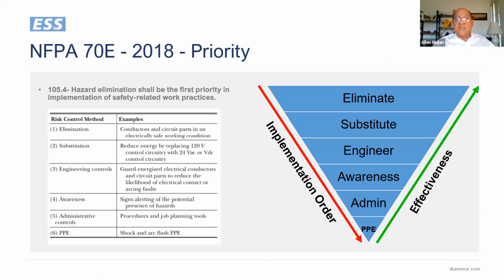The 2018, which is the latest version, has identified the priorities. This is new in 2018. It says use the hierarchy of control: elimination, substitution, engineering controls, awareness, administrative control, and PPE in that order. That's the implementation order. Obviously, the effectiveness is from PPE to elimination. So PPE being least effective and elimination being the most effective. However, when you're working around energized equipment, when you're doing lockout tagout, when you're creating electrically safe condition, when you're doing troubleshooting, awareness, administrative controls, and PPE are paramount to protect the electrical worker.